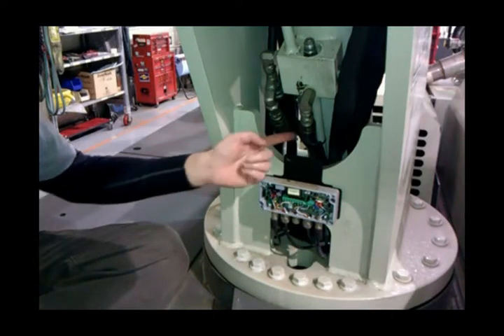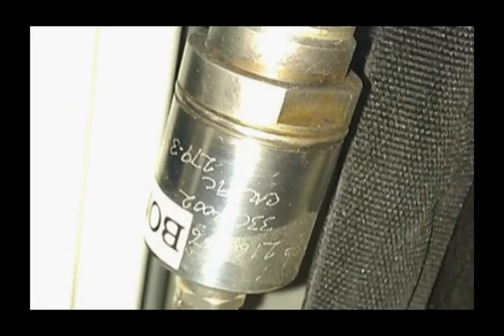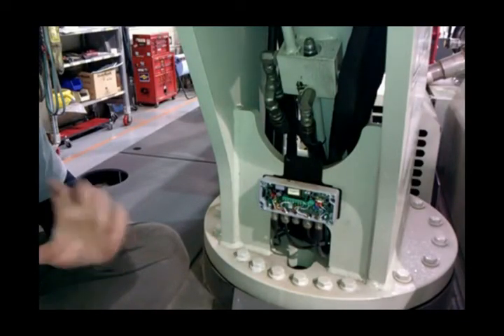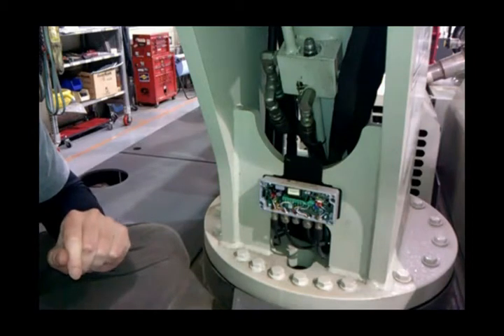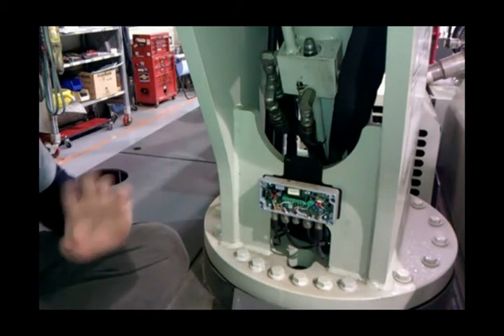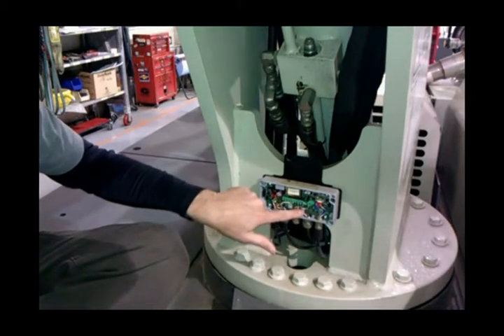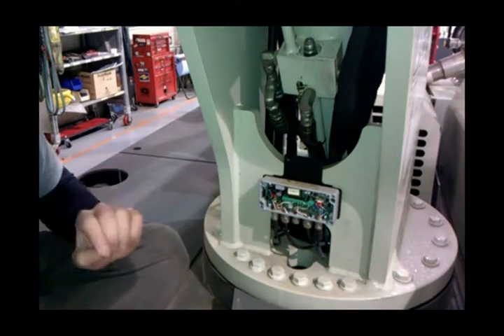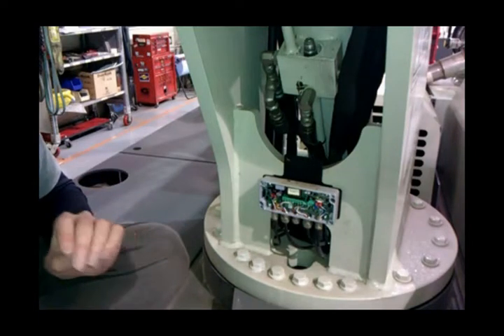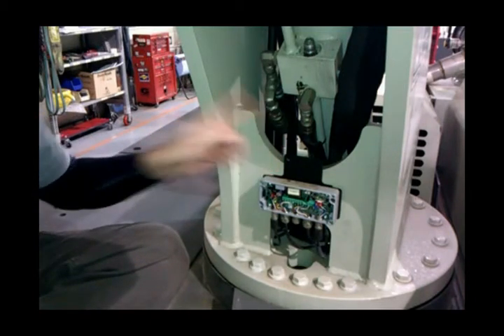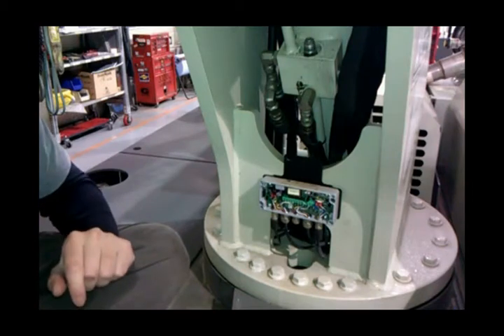What you also need to know is on the transducers themselves, there is an inscribed number. The one closest to the hydraulic fitting is the transducer calibration value for that transducer, such as 278.3. That's approximately what these will show. That is the span value. So when you go to span your transducer, you'll be coming over here, throwing the switch, and then you'll be going into the console under the span pressure transducer selection, and you'll be entering that value off of your transducer into the highlighted box. We're going to show you that in a few minutes.